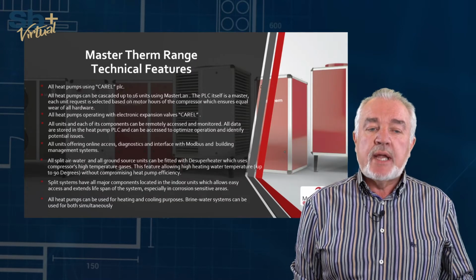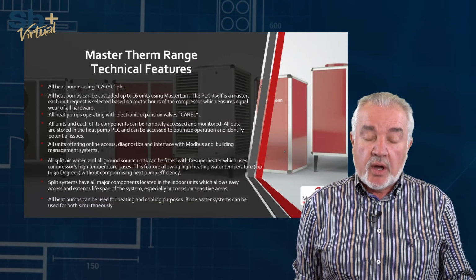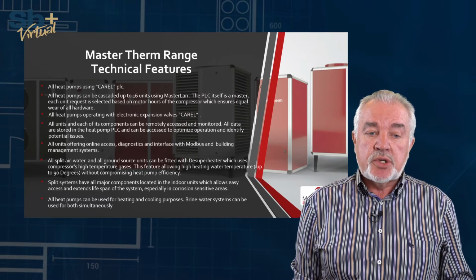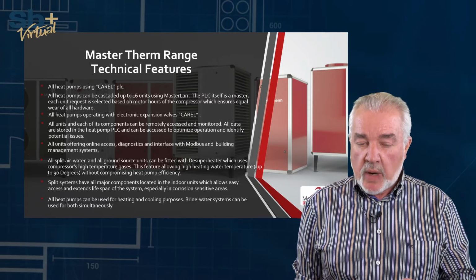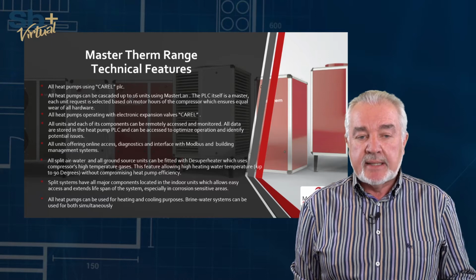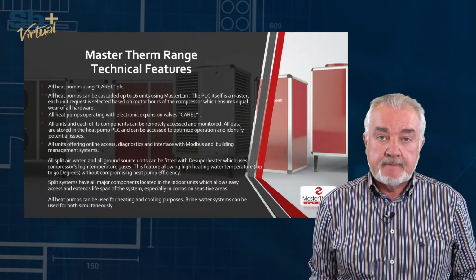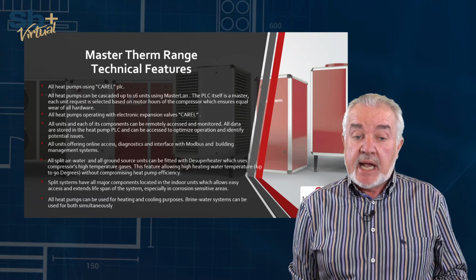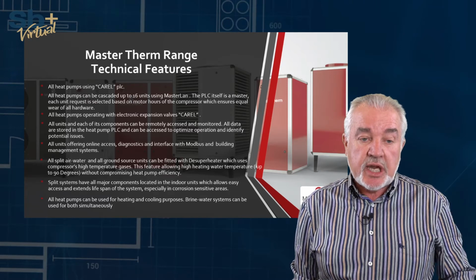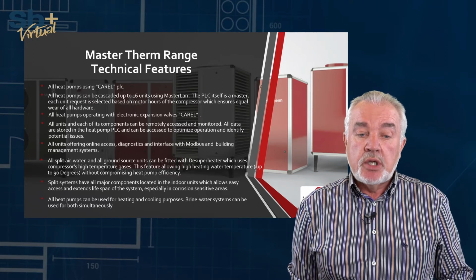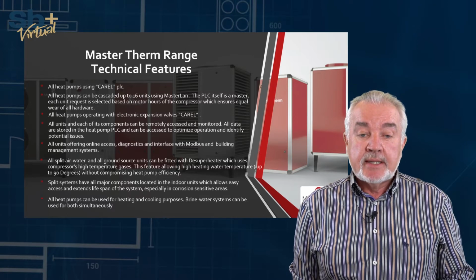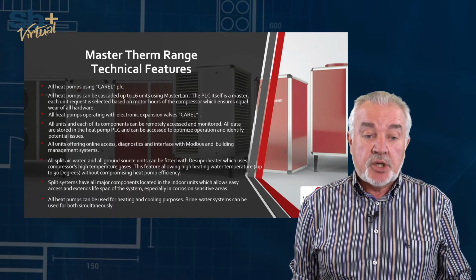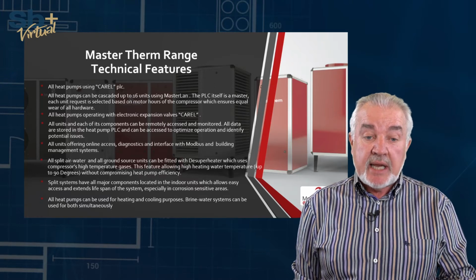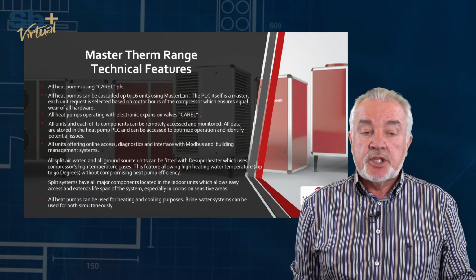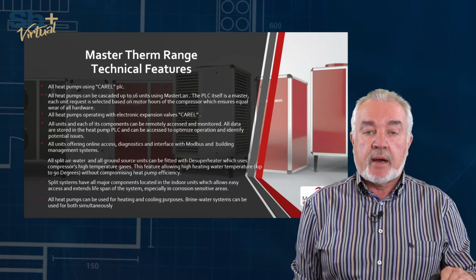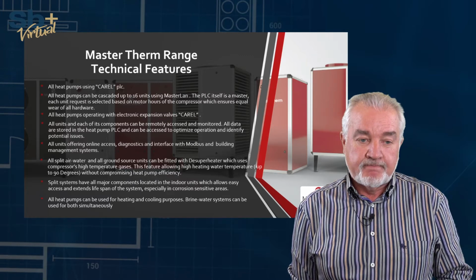To sum up some of the range's technical features, first of all MasterTherm heat pumps use Carel parts. Carel is a well-known, recognised leading brand in the refrigeration spares business. All of our heat pumps can be cascaded. In other words, they can be fitted in sequence up to 16 units using a master LAN controller. The PLC itself is a master, so each unit request is selected based on the motor hours of the compressor. So it ensures, if you like, equal wear of all of the hardware in a plant room.